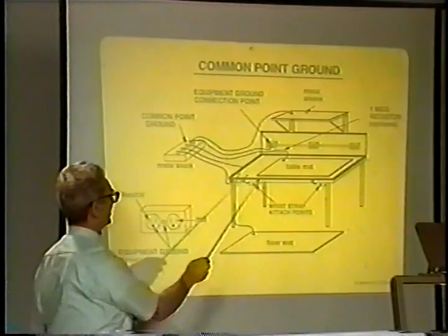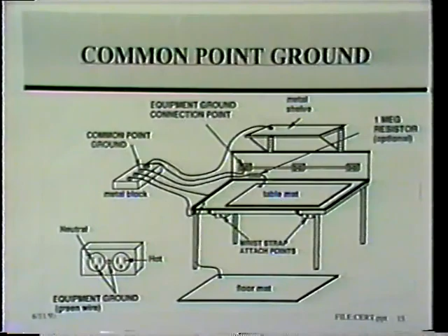This slide shows schematically what goes on at a workstation. We have a table mat that can have a resistor in it to limit the current going to the common point, but it's sufficient to drain off any charge from equipment or tools you put there. It is connected to the equipment grounding conductor.